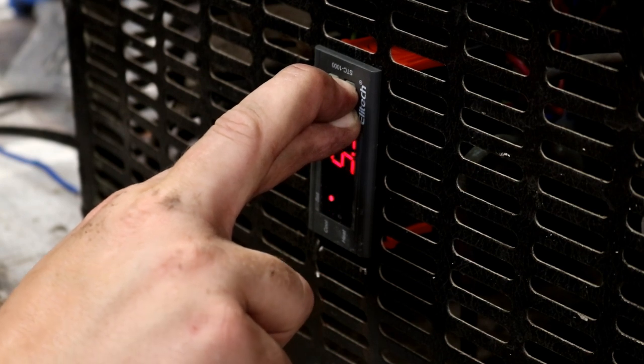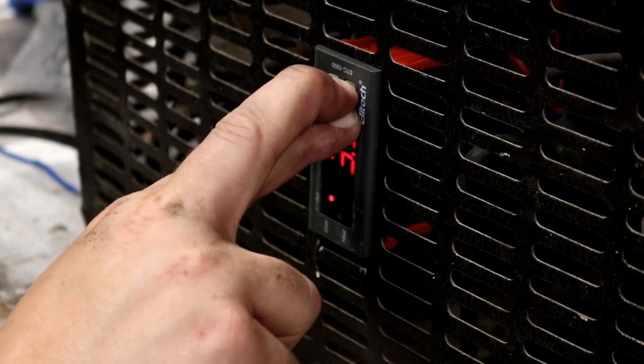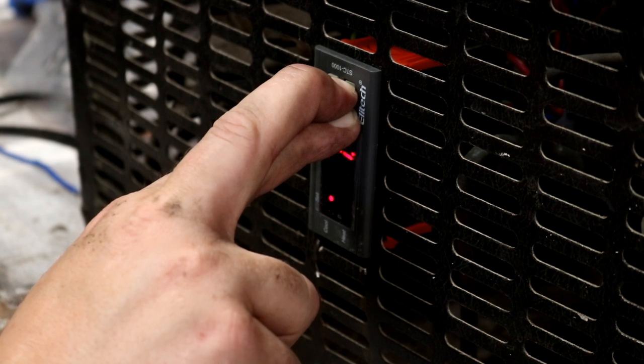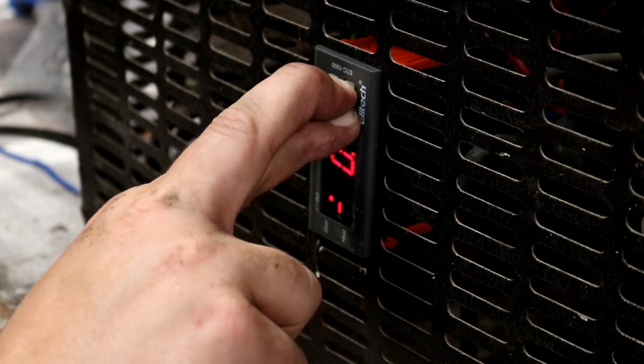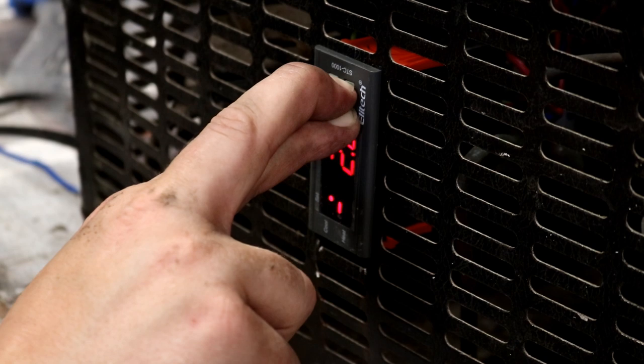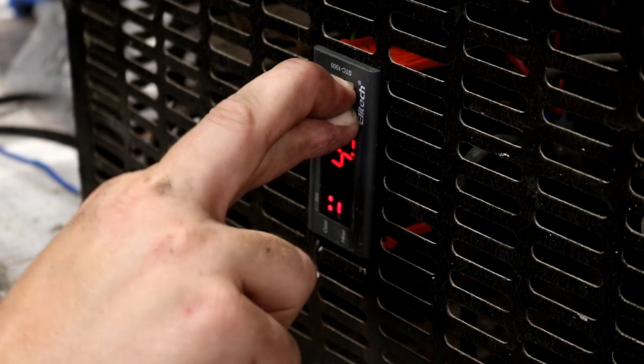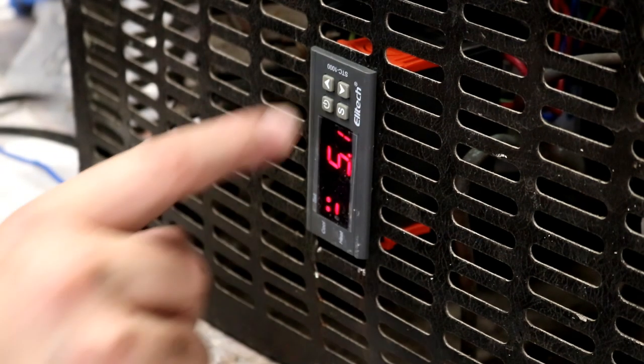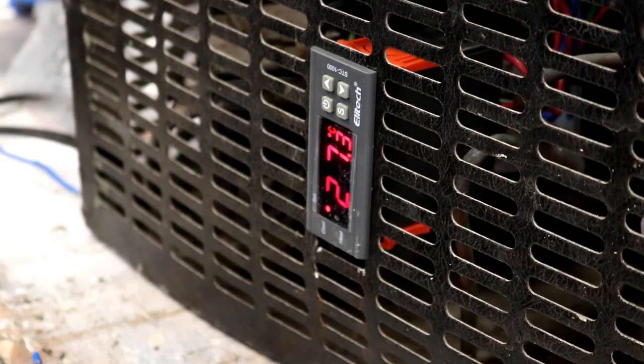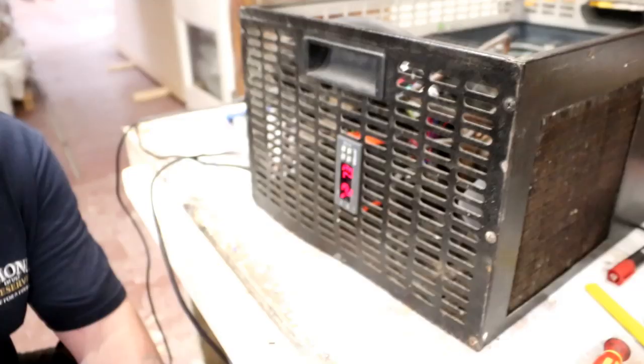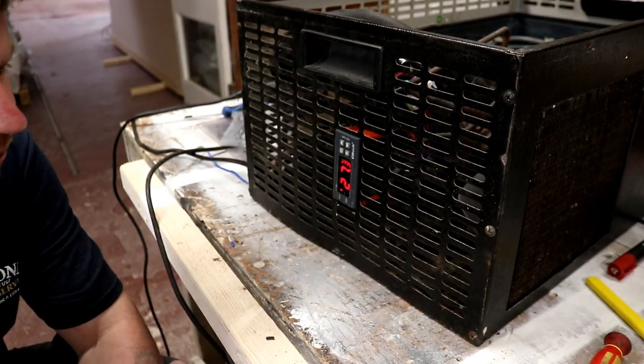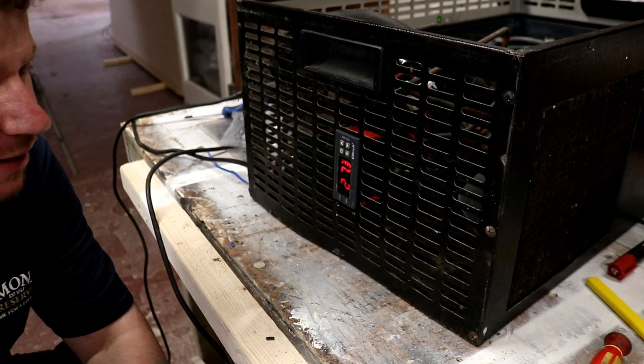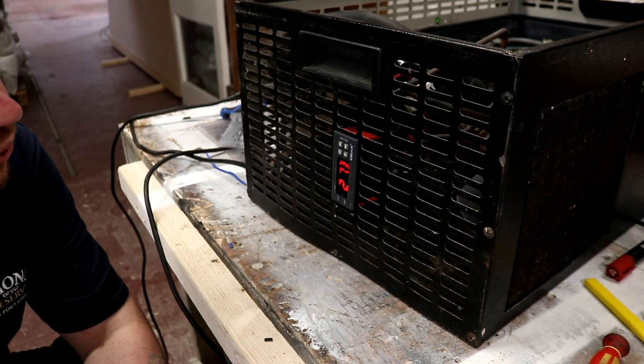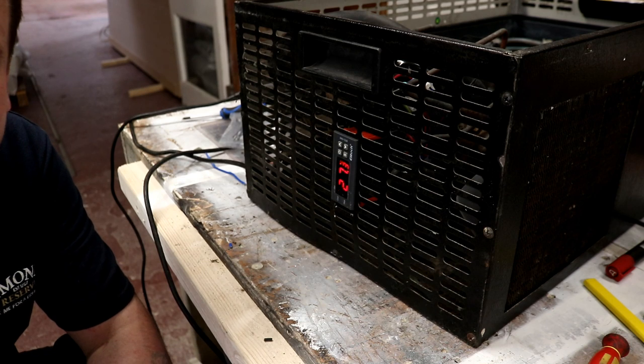Where we can fill it up with glycol and set this thing running in a few days' time when we've got all the cables and tanks finished. I think minus 5 is good. Press the power button again to lock that in. And that's it, folks, all done. That's how to rewire a Maxi 310 chiller with an STC 1000.